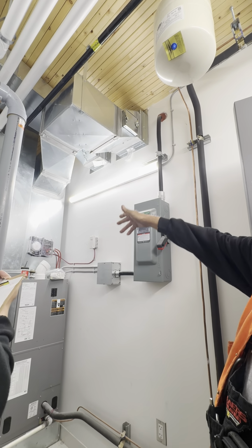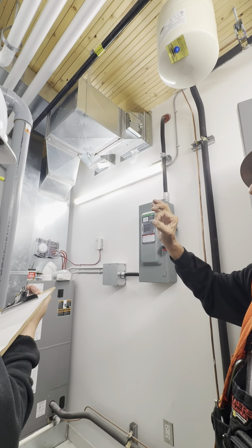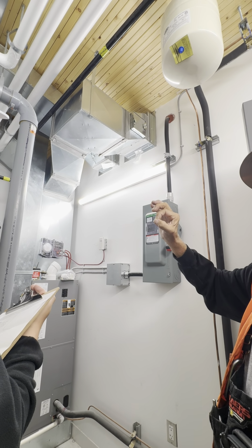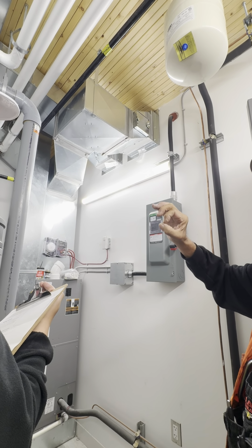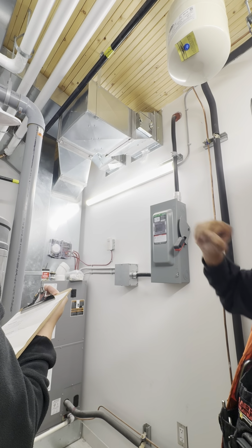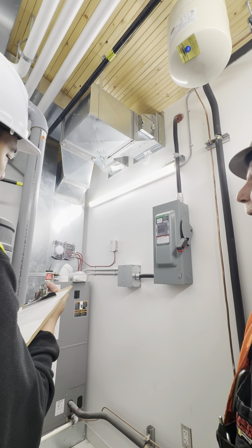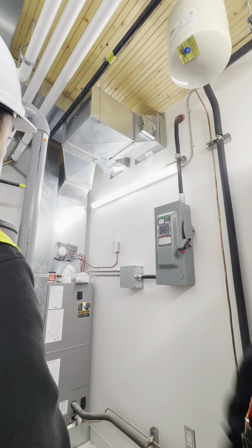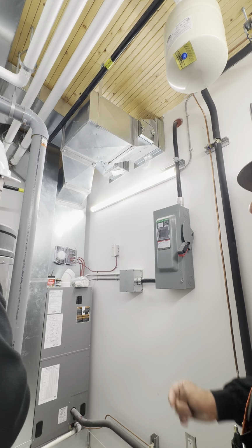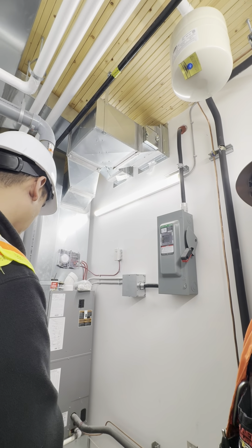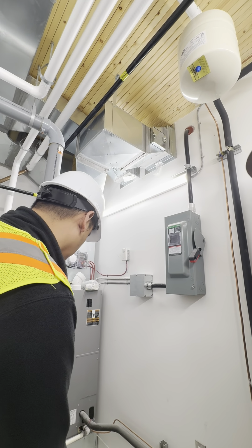So if you decide - and fusible links do deteriorate, okay? I don't know how long you guys have been doing this, but they deteriorate. So if the furnace keeps going on high limit, check the fire dampers, check the filters, then check the fire dampers, because more than likely the link went on a fire damper.